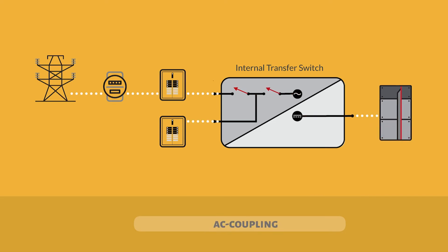Okay, now let's go through the same scenarios but this time adding an AC coupled grid-tied inverter. When retrofitting an energy storage system to an existing grid-tied system, the grid-tied inverter is moved from the main panel over to the protected loads panel. While grid connected, the hybrid battery-based inverter is in a pass-through state providing the grid-tied inverter the grid source. Once the grid-tied inverter has completed its five-minute source verification, it will begin pushing solar energy to the home. Anything not consumed by the loads will be exported back to the grid.